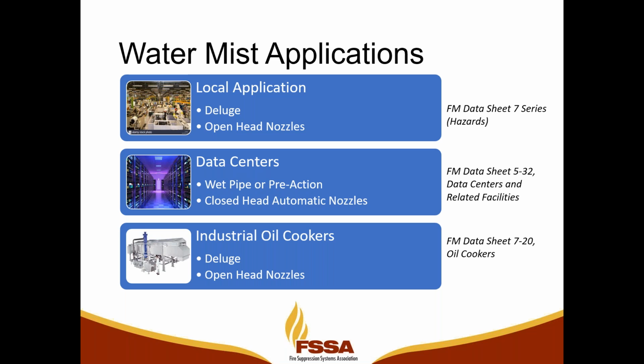CO2, you have to take a lot of extra precautions to make sure you give people a chance to exit the space before the system even goes off. So a lot of people are opting to use water mist, and water mist works so well on oil cookers because you have to do two things. You have to knock the flames down as quickly as possible, and then you've got to cool the oil to below its auto ignition temperature as quickly as you can so that you don't get reignition.